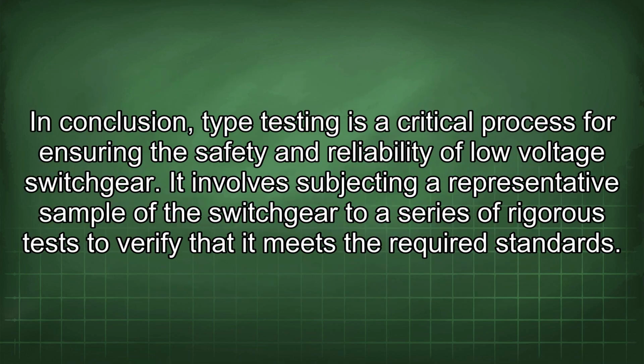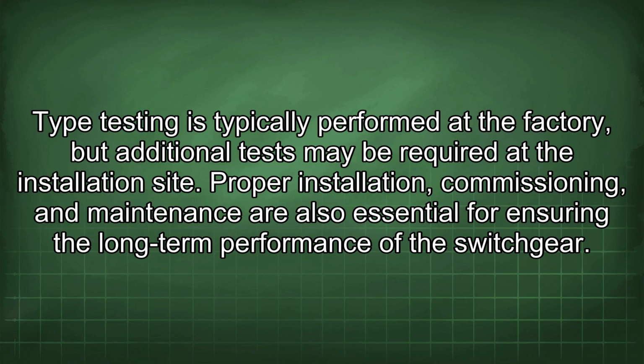In conclusion, type testing is a critical process for ensuring the safety and reliability of low-voltage switchgear. It involves subjecting a representative sample of the switchgear to a series of rigorous tests to verify that it meets the required standards. Type testing is typically performed at the factory, but additional tests may be required at the installation site. Proper installation, commissioning, and maintenance are also essential for ensuring the long-term performance of the switchgear.